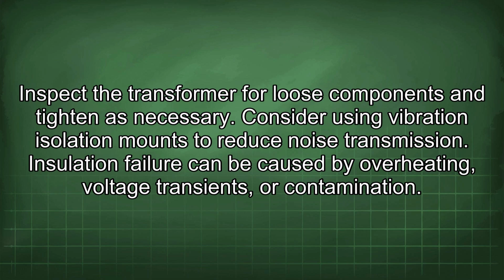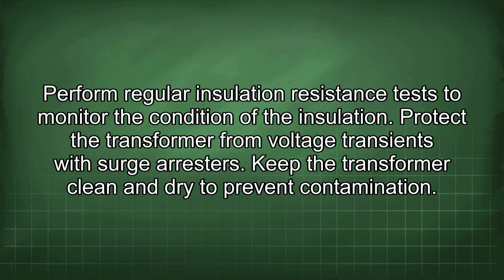Insulation failure can be caused by overheating, voltage transients, or contamination. Perform regular insulation resistance tests to monitor the condition of the insulation. Protect the transformer from voltage transients with surge arresters. Keep the transformer clean and dry to prevent contamination.